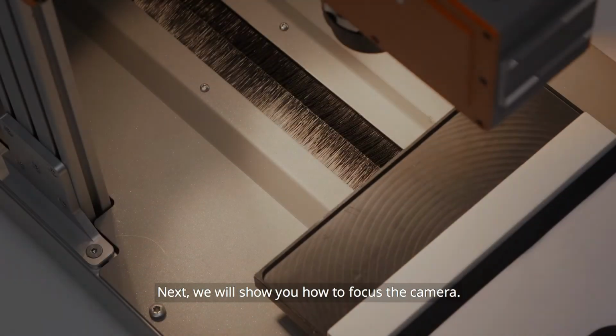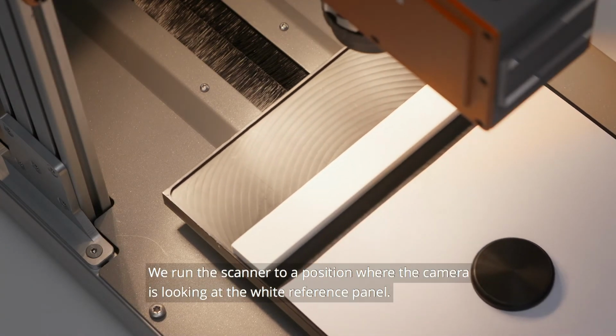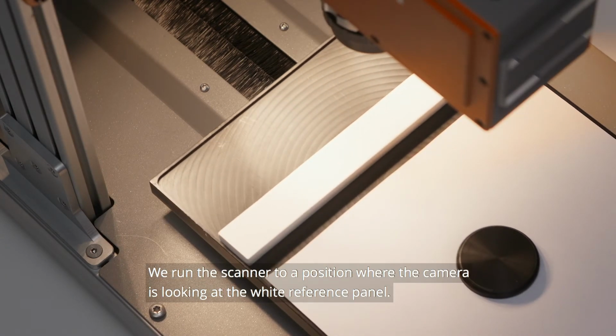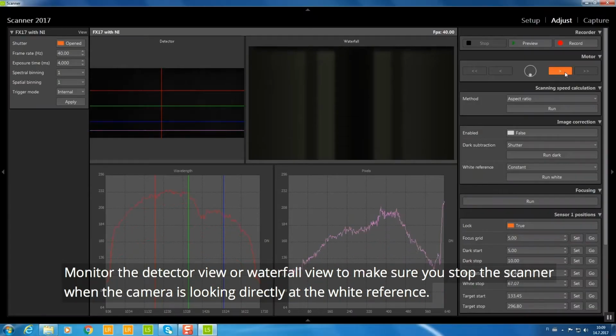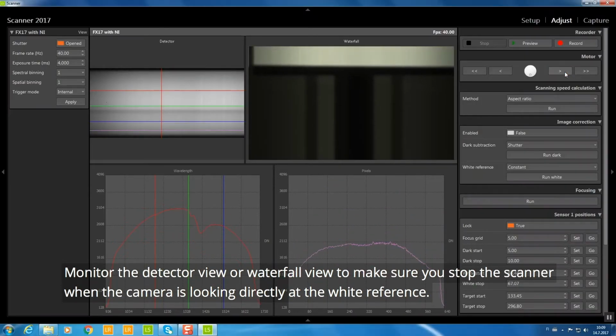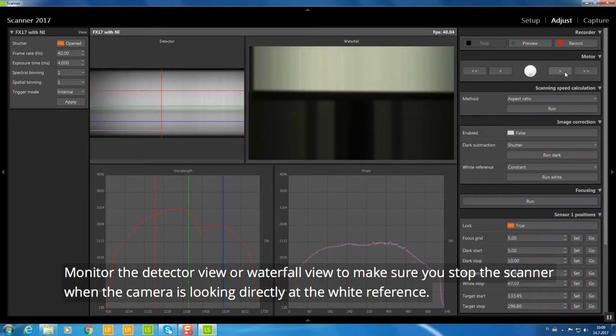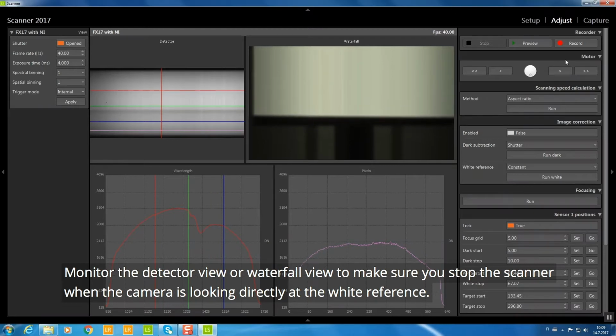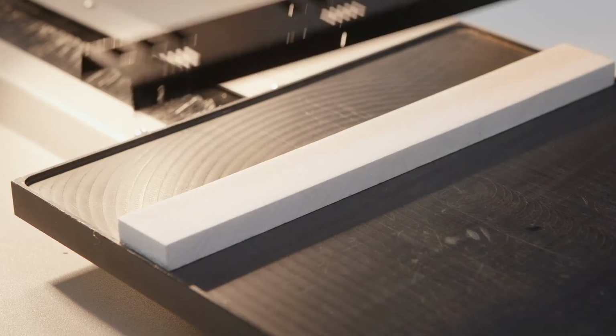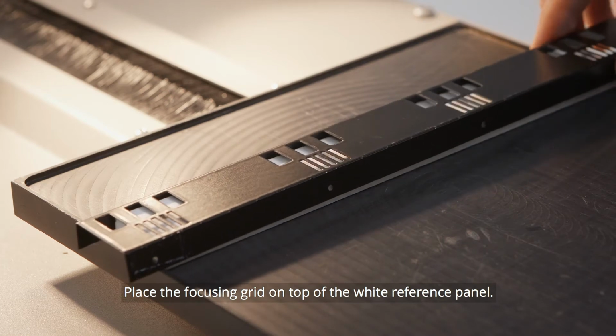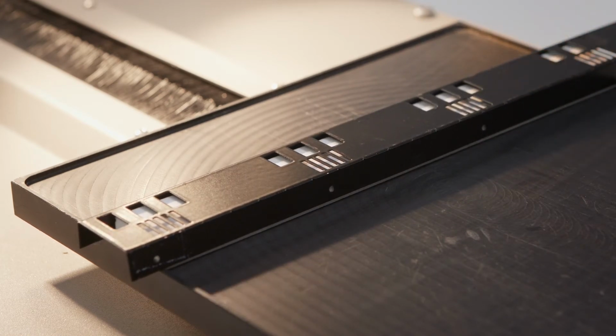Next, we'll show you how to focus the camera. We run the scanner to a position where the camera is looking at the white reference panel. Monitor the detector view or waterfall view to make sure you stop the scanner when the camera is looking directly at the white reference. Place the focusing grid on top of the white reference panel.